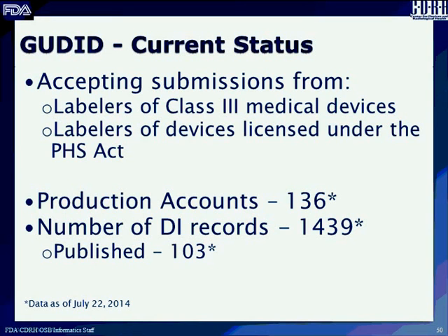If you have a test account and a production account in GUDID, if you enter records into the test system, as we clearly say here, these submissions made to this system will not meet your GUDID submission requirements. So be careful if you are a web interface user and you're entering records. Make sure you use the correct GUDID to enter your records. So since I'm demoing, I will be using the test system. I'm going to log in as a LDE user.